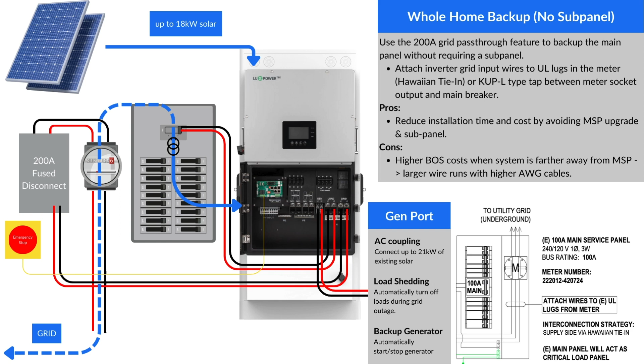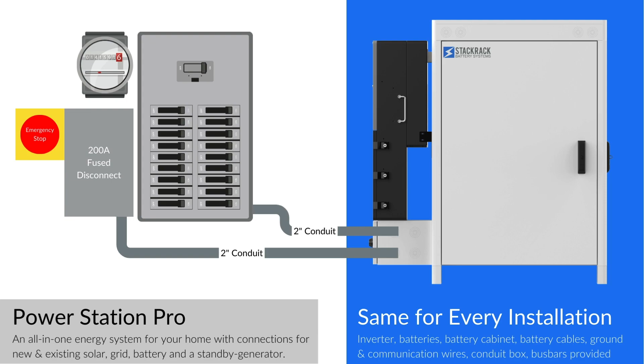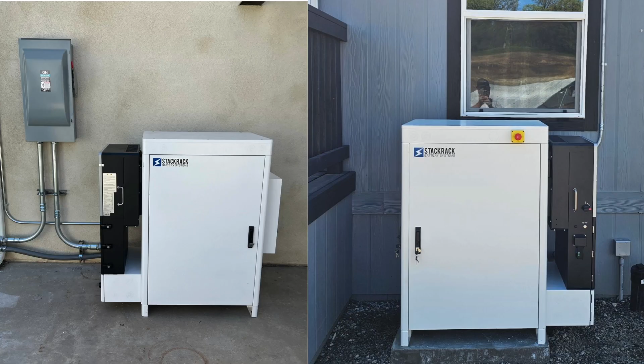You can program the gen port to be a smart loads output and then shed these loads during a grid outage. And if the customer wants to run the central air conditioning units during a grid outage, we would recommend soft start devices. And this is what the installation will look like. You will need to run 2 2-inch conduits due to the wire sizes, but everything else remains the same. And here are a few pictures of PowerStation Pro installations.